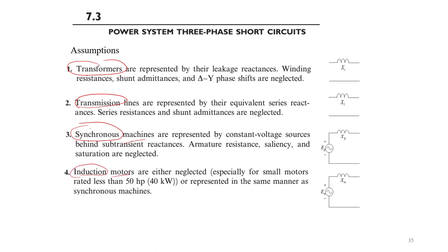The source of energy in a power system mostly comes from the synchronous machine, and most of the loads are represented by induction motors. The transformer is represented by the leakage reactance. For large transformers in transmission systems, we express the transformer by just a single reactance — the leakage reactance. The resistance, shunt admittance, and phase shifting due to different primary/secondary connections are neglected.